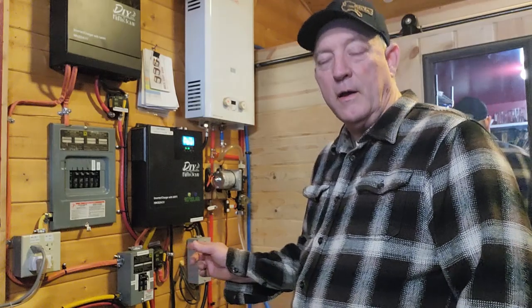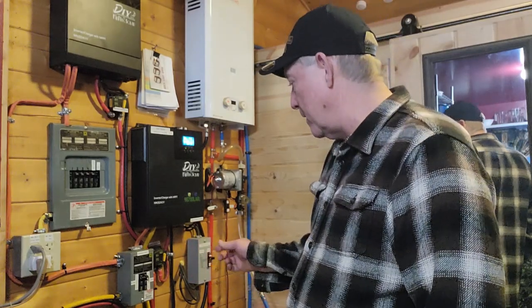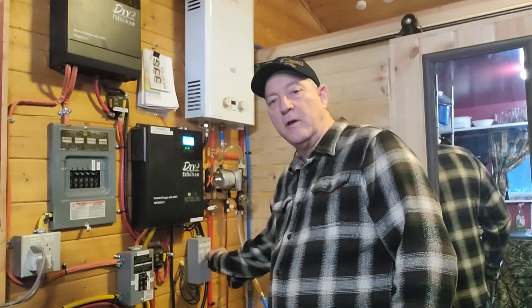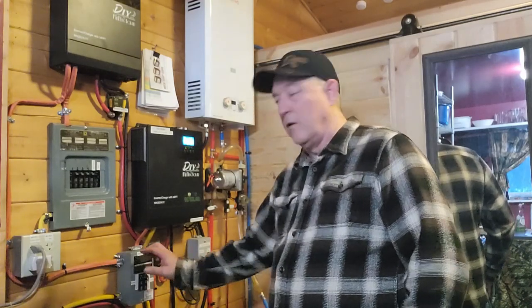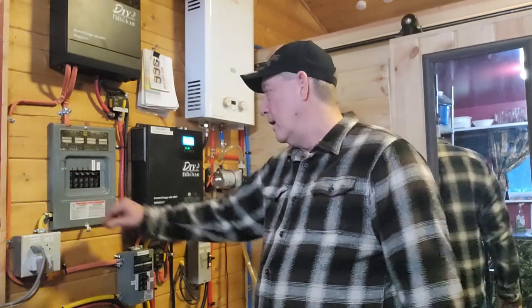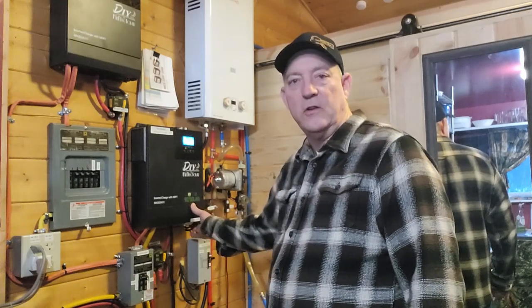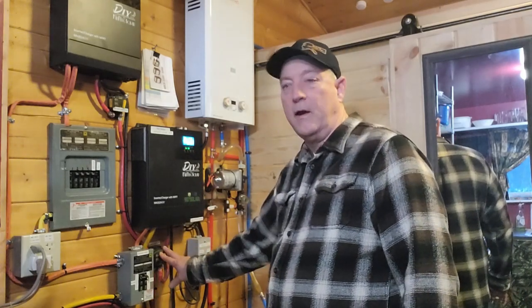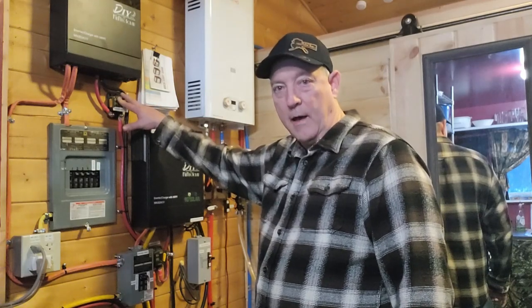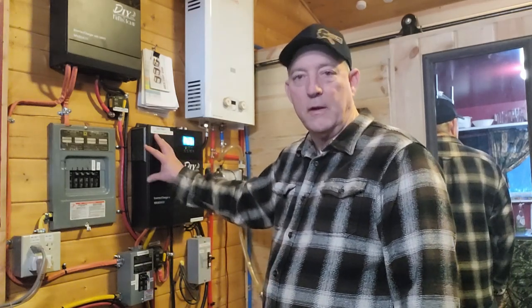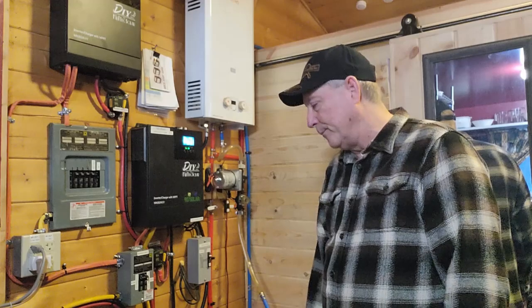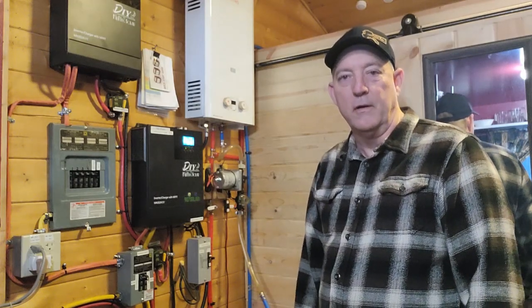One thing I did fail to mention when I talked about protection: I have a means of disconnect from the solar and the generator for each circuit run through the house, and each inverter has its own disconnect too. Right here and right here, I have disconnects that feed down to the batteries, so I can shut the batteries down and work on other aspects of this without any backfeeding or anything potentially getting shocked or hazardous.